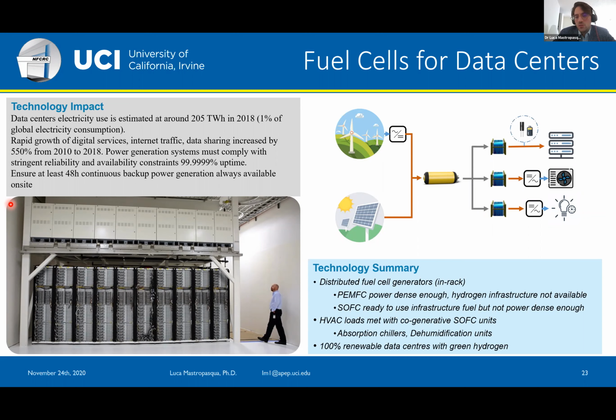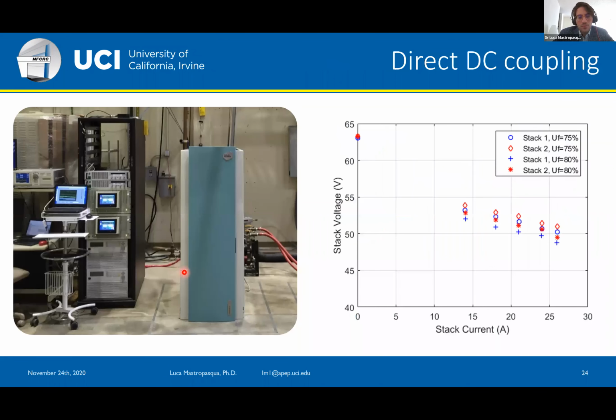So what we first did was test solid oxide cells coupled with server racks. This is an example of the test stand we put together using a 2.5 kilowatt electric commercial solid oxide fuel cell, with a direct DC coupling to a server rack. We removed all the power electronics from the fuel cell and directly coupled the output of the two stacks that make up this system to the DC input of the servers.